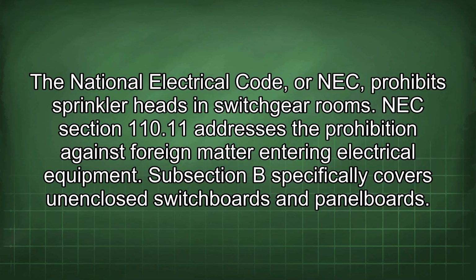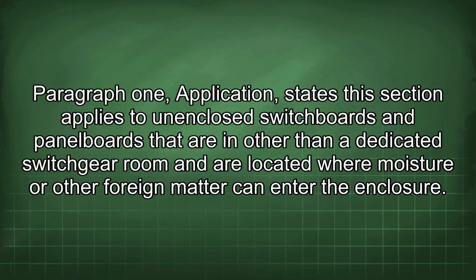The National Electrical Code, or NEC, prohibits sprinkler heads in switchgear rooms. NEC Section 110.11 addresses the prohibition against foreign matter entering electrical equipment. Subsection B specifically covers unenclosed switchboards and panel boards. Paragraph 1, Application, states the section applies to unenclosed switchboards and panel boards that are in other than a dedicated switchgear room and are located where moisture or other foreign matter can enter the enclosure.